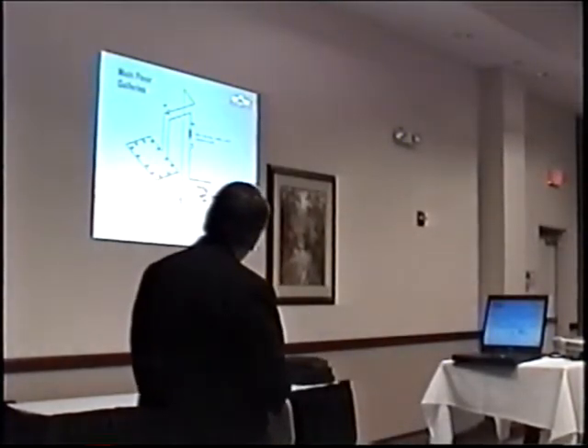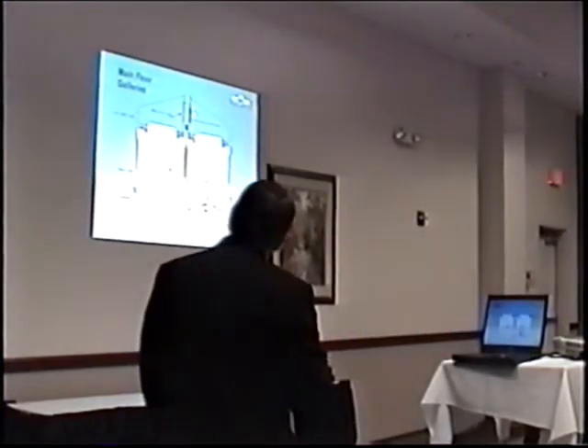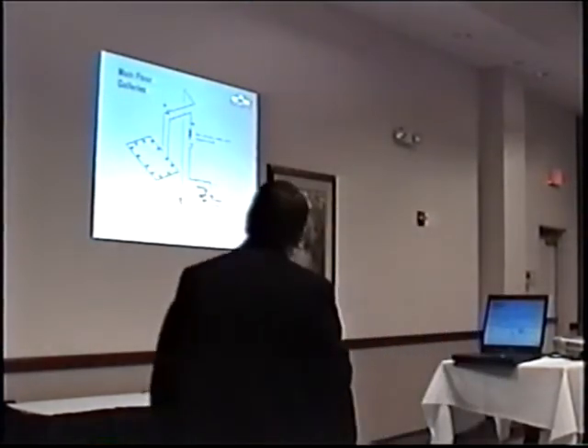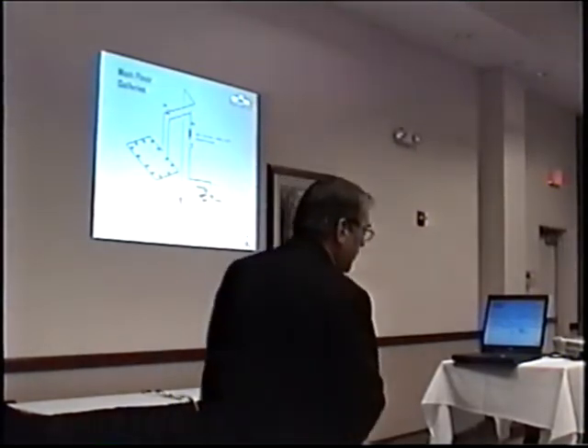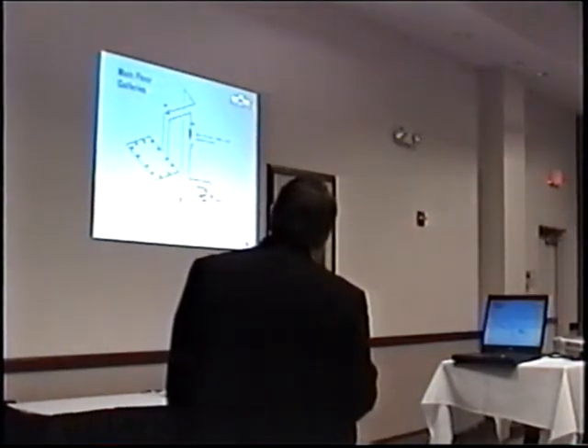The way the system was structured, I basically had the pump in the basement, the risers up to the lay light level, I've got the deluge valves up there, so I have water up to this point, deluge valve. Then I have these low trap sections around each of these lay light areas. And again, using the end-of-line check valve, the pump starts, the valve opens, the water goes around the loop, through the check valve, gets the air out beyond the nozzle portion, and then fills right up to the closed end-of-line drain valve.